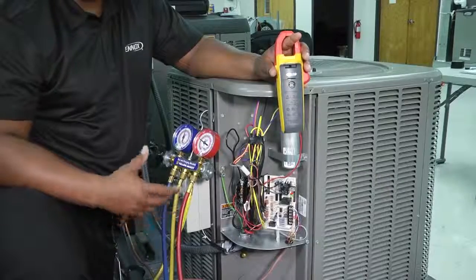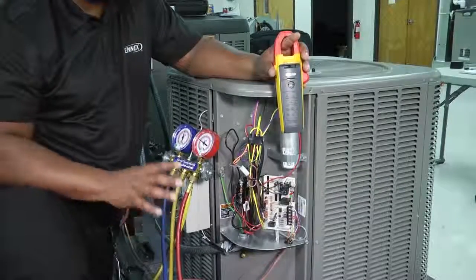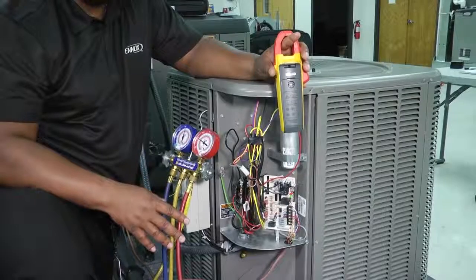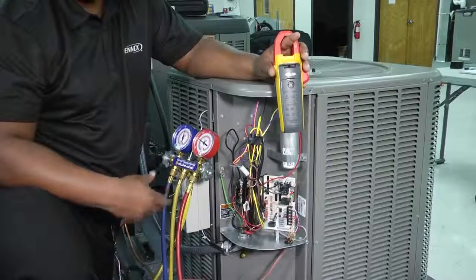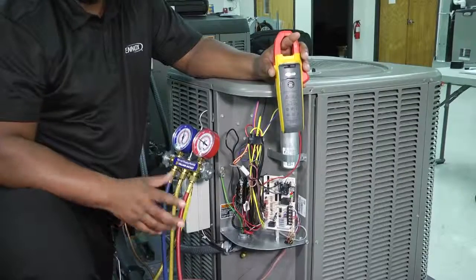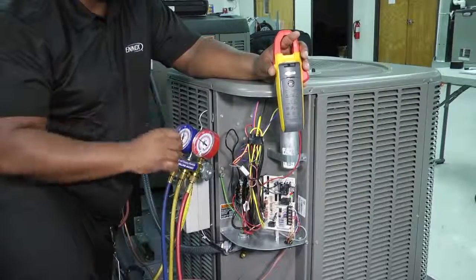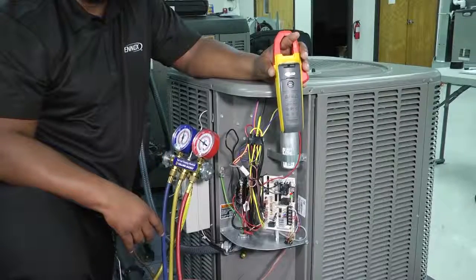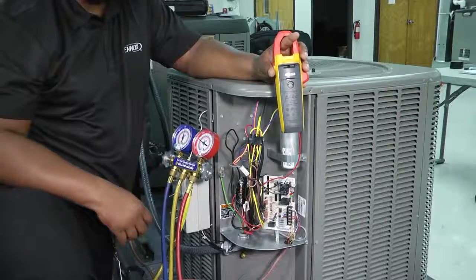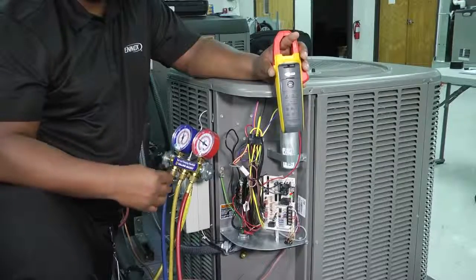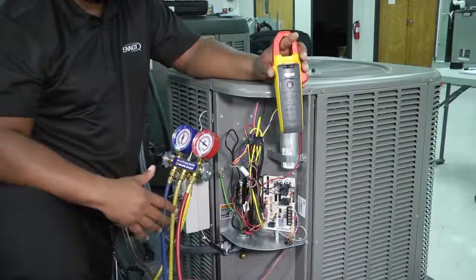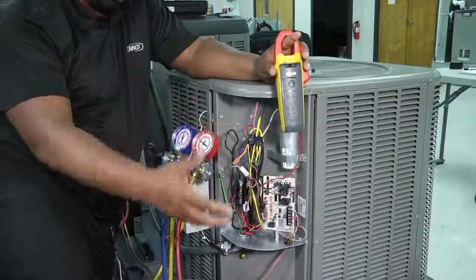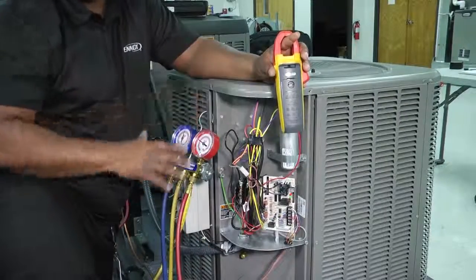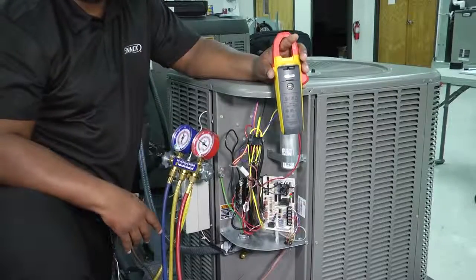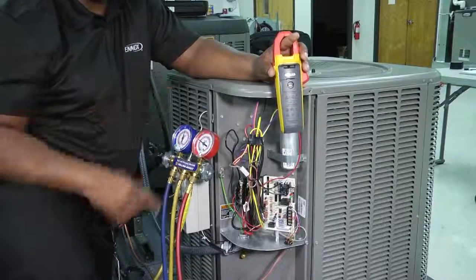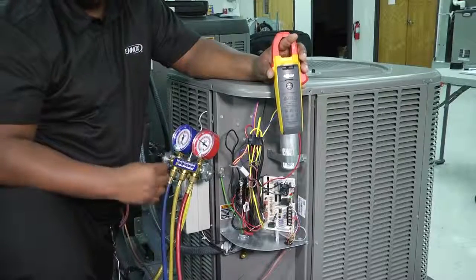Now our superheat is going to be determined, how we look at that number, based on whether or not we have a fixed orifice metering device or if we have a TXV as our metering device. Those two numbers are going to vary based on which type of metering device we have in our system. We know that a TXV is designed to maintain a constant superheat of 10 to 15 degrees. So by that, we're going to charge our system by subcooling because our TXV is going to try to regulate the temperature for us.